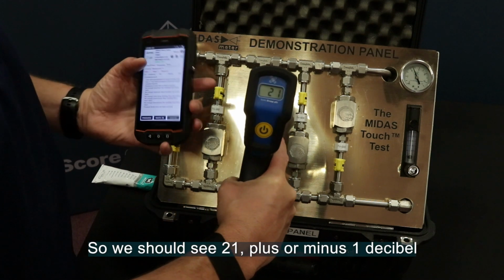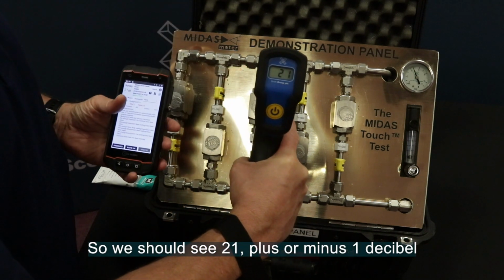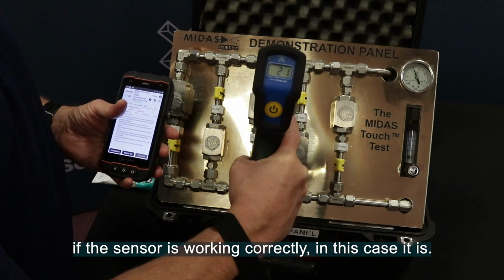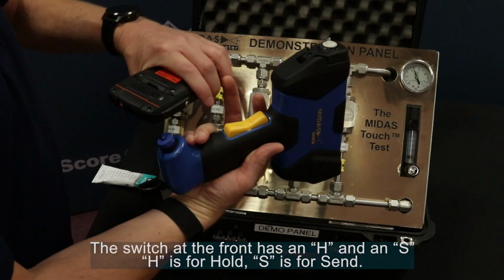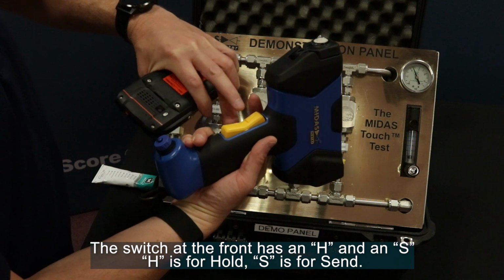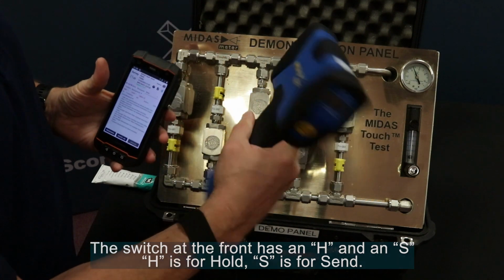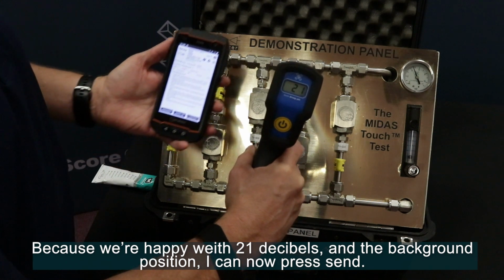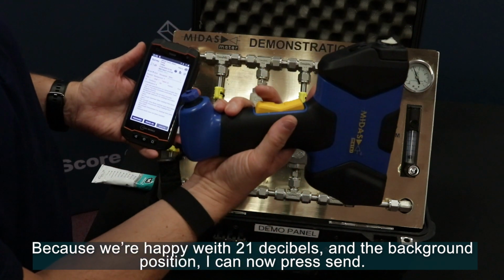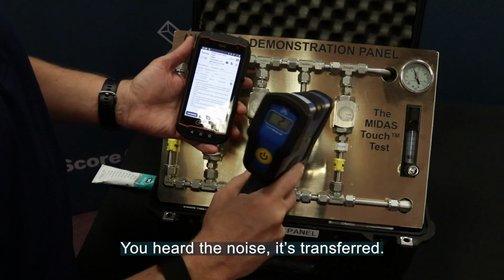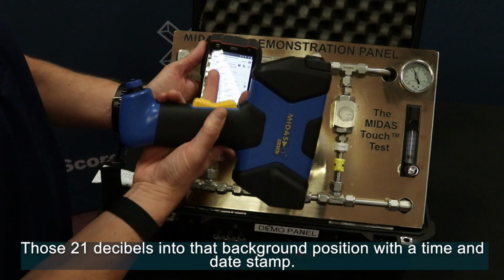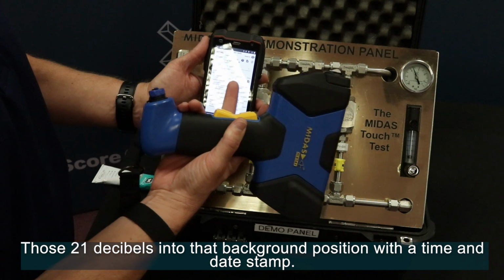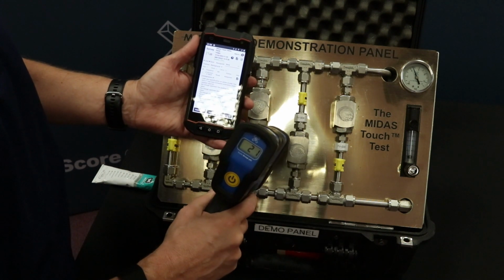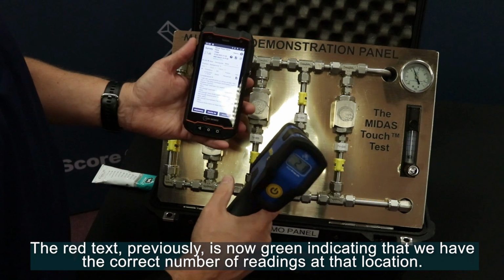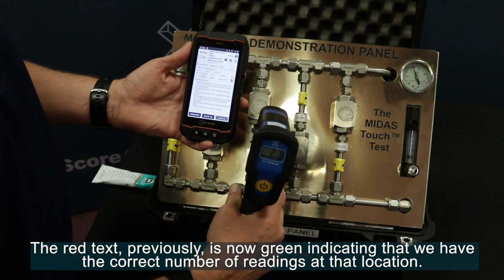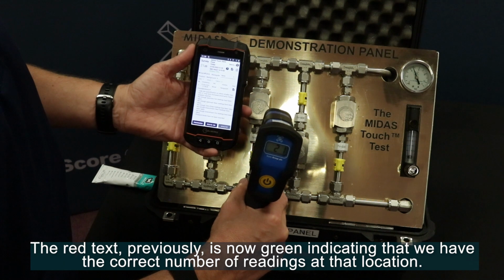So we should see 21 plus or minus 1 decibel if the sensor is working correctly, and in this case it is. The switch at the front has an H and an S. H is for hold, S is for send. Because we're happy with 21 decibels at the background position, I can now press send. You hear the noise, it's transferred those 21 decibels into that background position with a time and date stamp. The red text previously is now green, indicating that we have the correct number of readings at that location.